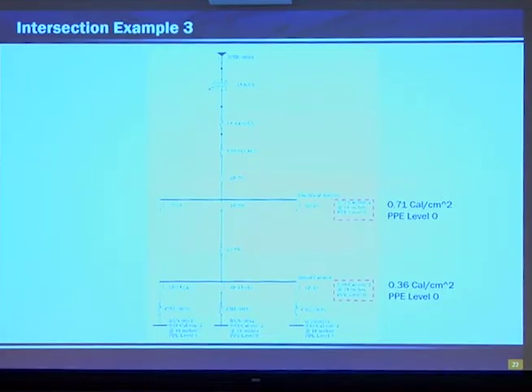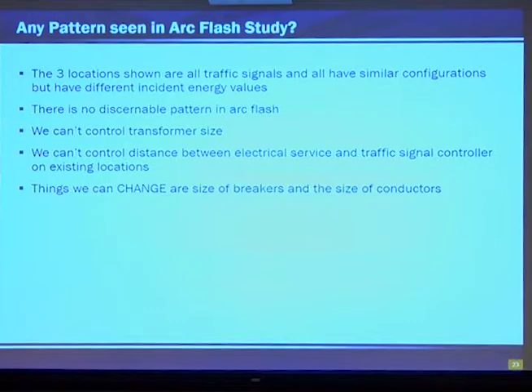And for this final intersection, we had 0.71 calories per centimeter squared at the service and 0.36 calories per centimeter squared at the signal cabinet. Both of these had PPE levels of 0. For all three of these locations, all of these were traffic signals, and all of them had similar configurations, but all of them had different incident energy values. All of them also had different PPE values.